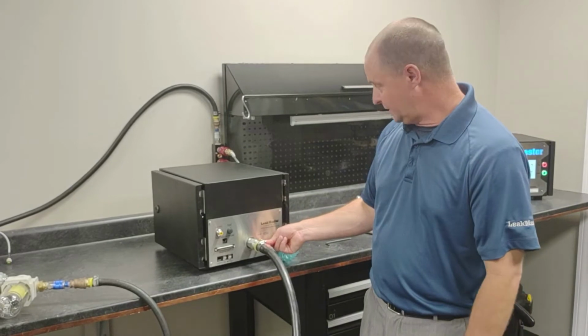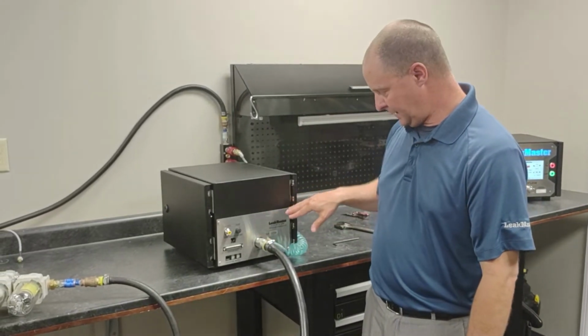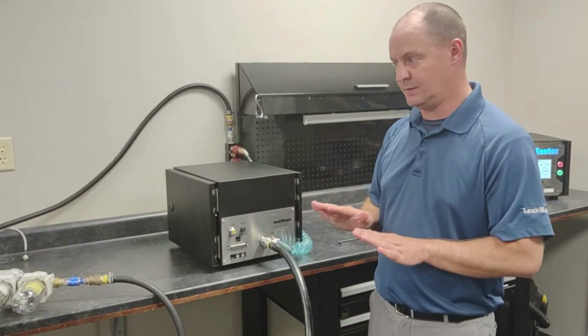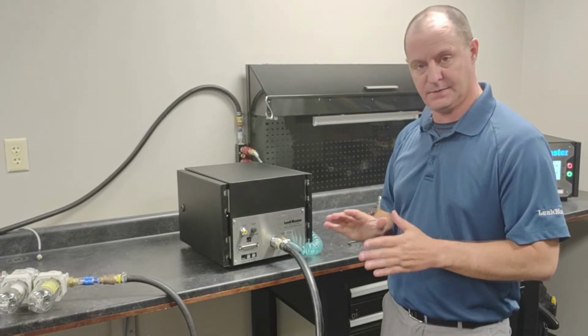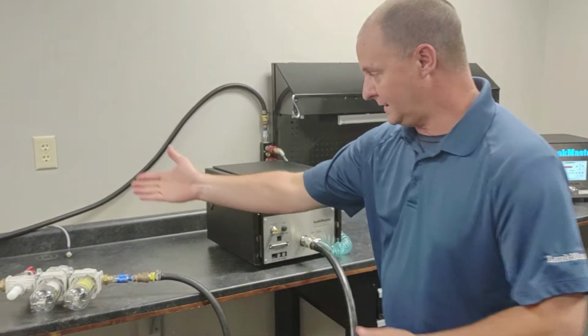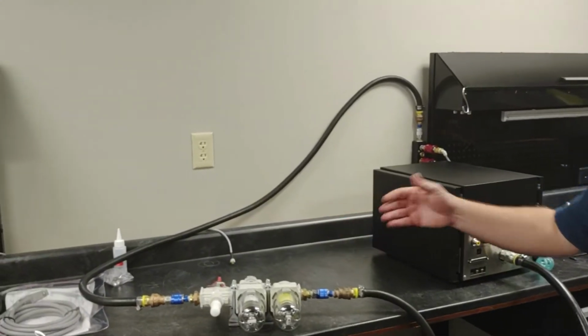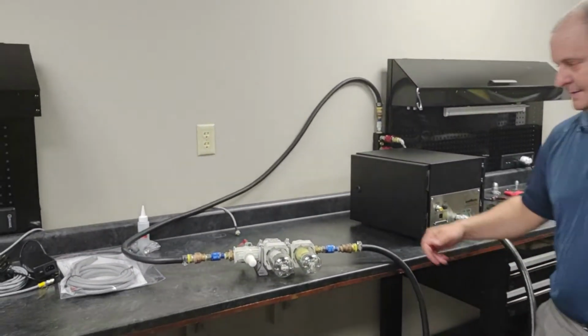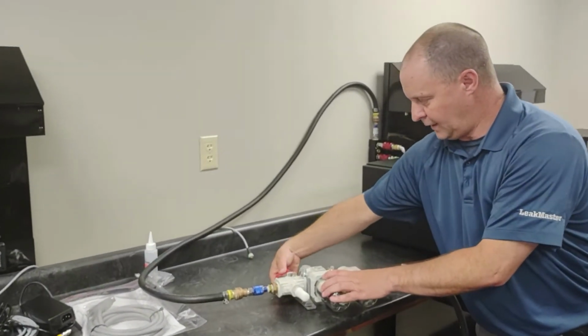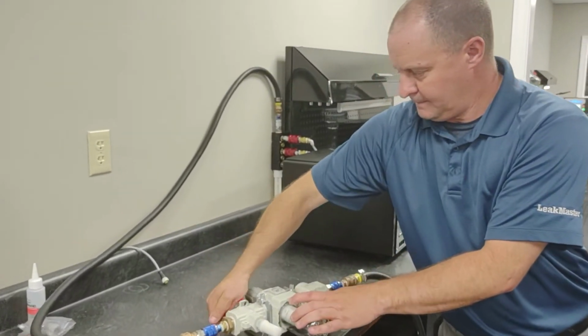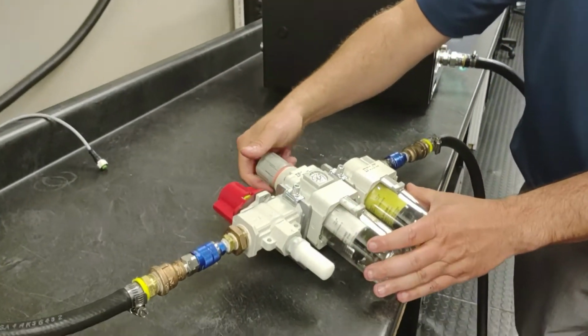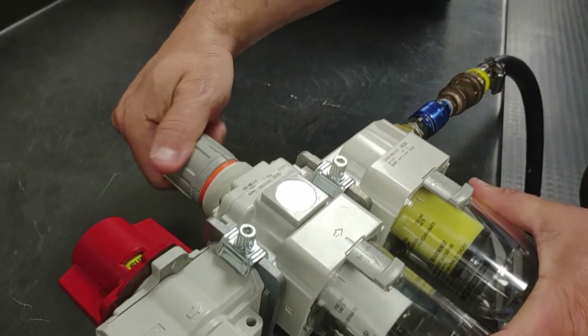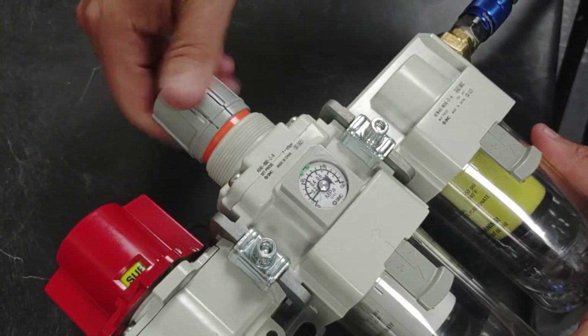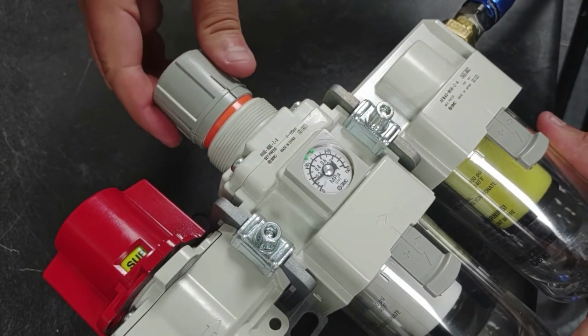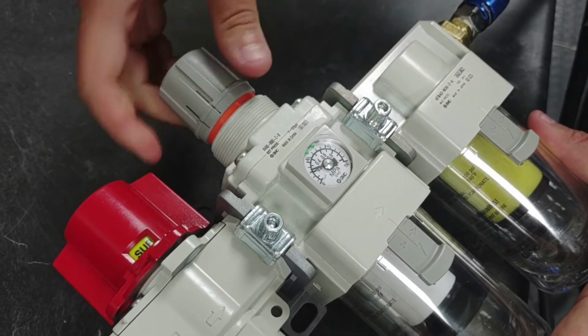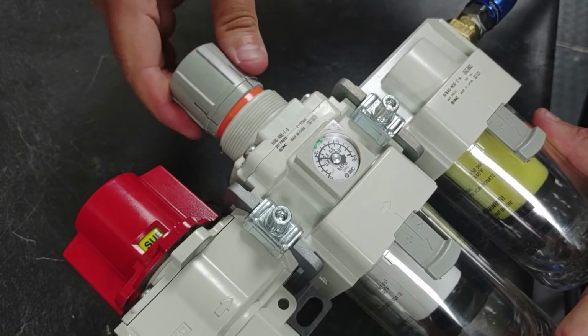We just brought pilot pressure up, so we've got pilot pressure supplying our valves, so it's going to actuate our internal pneumatic valves properly. Now we're going to bring air on to our air prep unit, which is going to deliver air to our ballast tank. So if I open up my supply valve, you can hear the air starting to fill my ballast tank through the check valve. And I'm going to run this up to 60 psi.